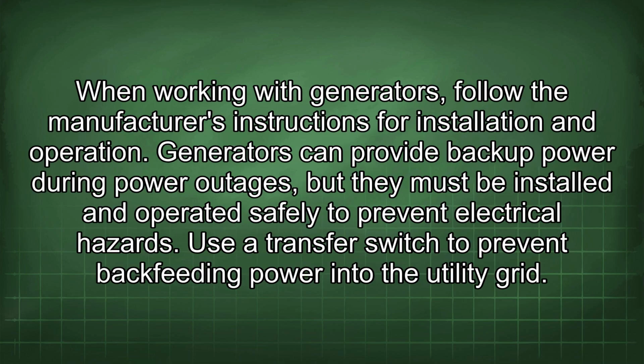When working with generators, follow the manufacturer's instructions for installation and operation. Generators can provide backup power during power outages, but they must be installed and operated safely to prevent electrical hazards. Use a transfer switch to prevent backfeeding power into the utility grid.